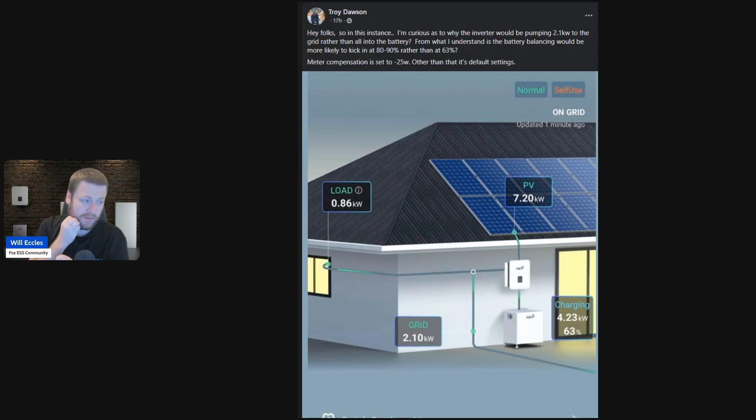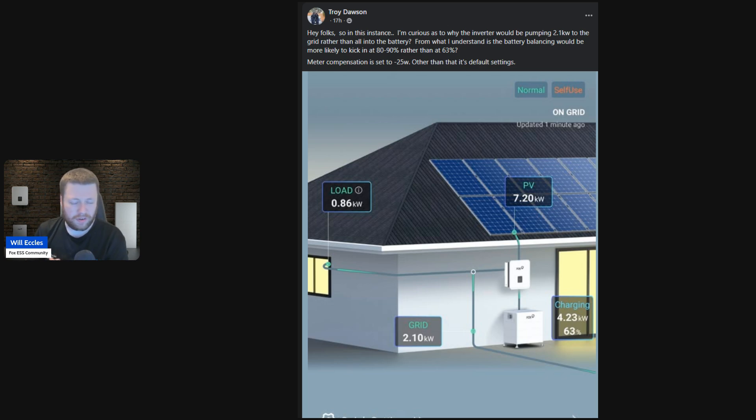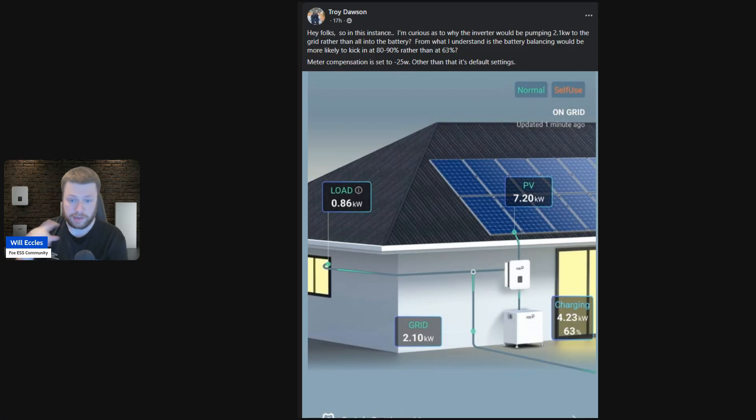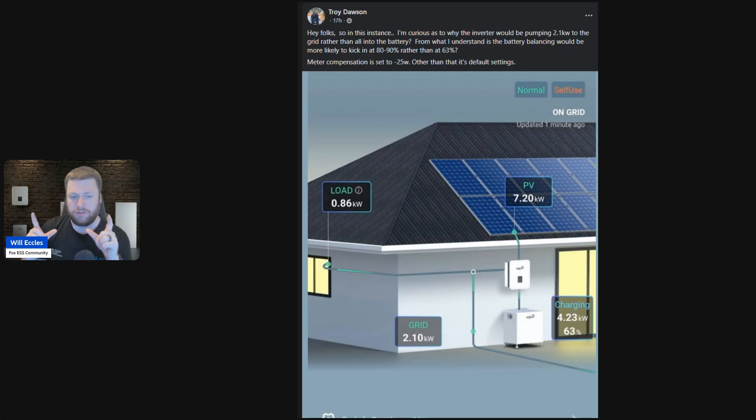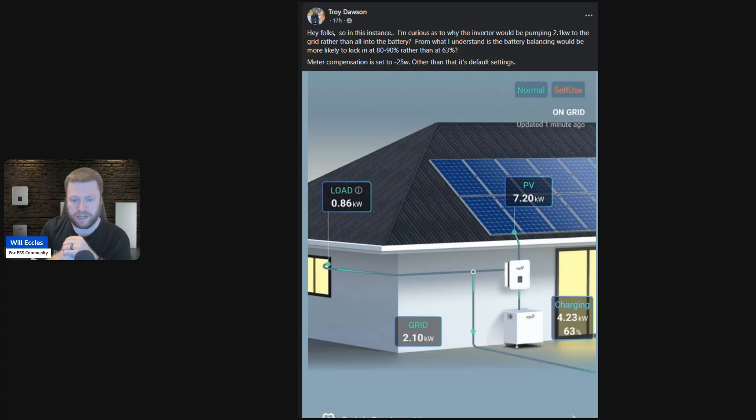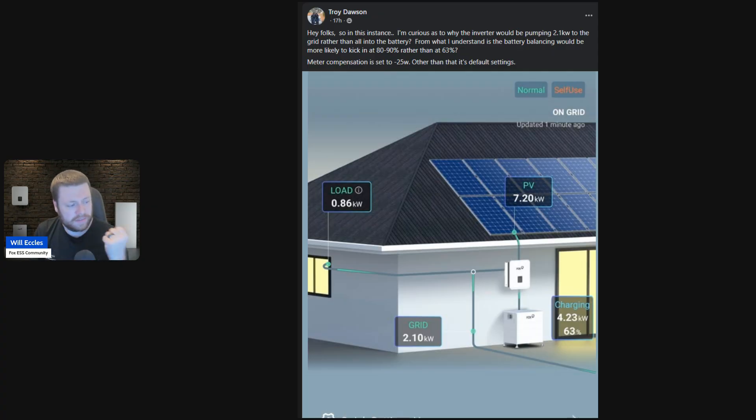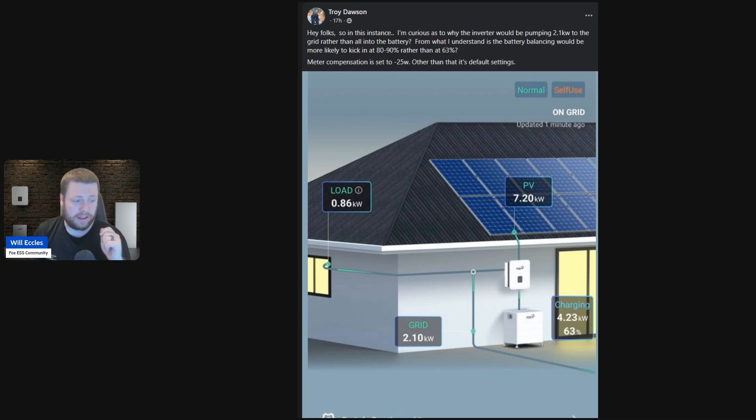Let's assume that it's not temperature related and that the temperature for this is well above the typical 12 to 15 Celsius. Below that, we start to see the performance slowly reducing. I do have a separate video if you look at my channel that has the battery algorithm in terms of what amps at what temperature at what state of charge. So have a look there if you're interested in really understanding what the charge curve characteristics and algorithm are. So if it's not state of charge and it's not temperature, what else could it be? It's most likely either inverter or battery limited.